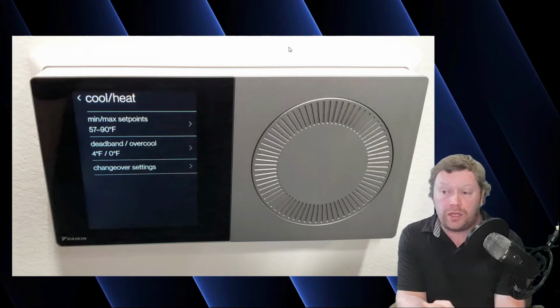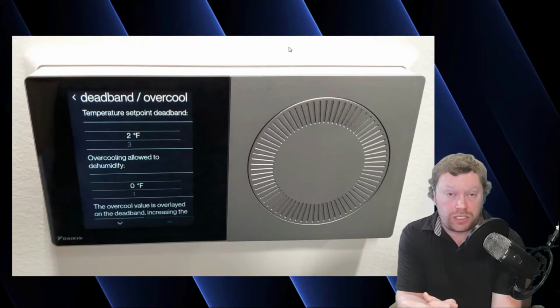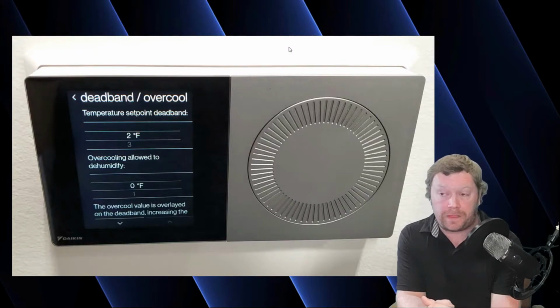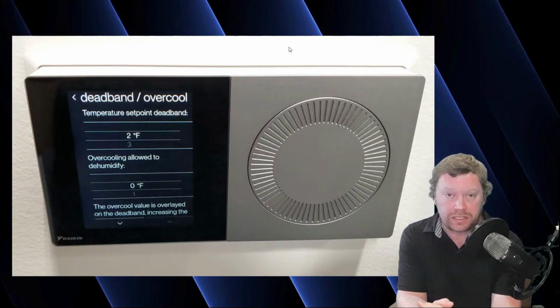Your deadband, I do want to talk about your deadband. So this is your set point differential. So if my heat set point is 70 and I set my deadband to 2 degrees, it's going to make my cooling set point 72. So your heating and cooling set point are always at least 2 degrees apart. You can always widen those set points manually at the home screen of the thermostat, but 2 degrees, if that's what you set on your deadband, is as tight as your 2 set points can go.